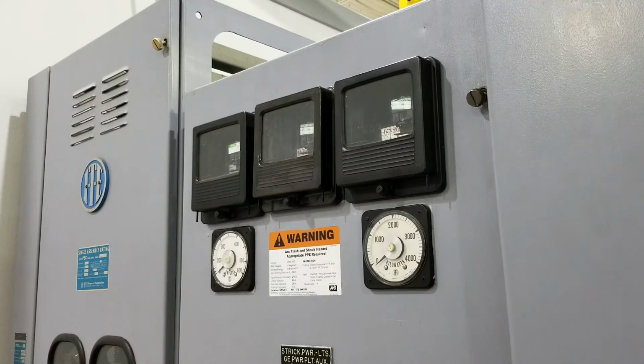Again, we talk about the same things we talked about with the GE relay, and that is we need to inspect the cover and glass, make sure they're intact and environmentally sound to keep things out of the relay, and then we'll show you how we go ahead and remove the relay from the switchgear.